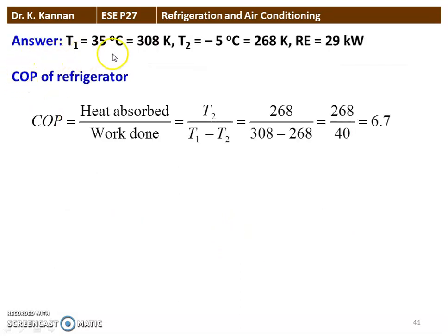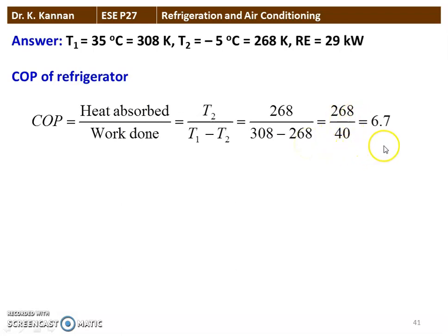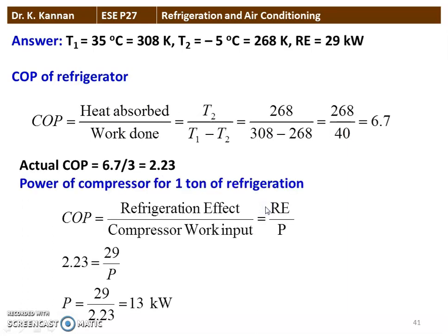The temperatures are T1 equal to 35 degree Celsius, which is 308 Kelvin; T2 equal to minus 5 degree Celsius, which is 268 Kelvin. The refrigeration effect equals the heat leakage, which is 29 kilowatts. The COP of the refrigerator based on temperature: COP equals minimum temperature divided by the temperature difference, so 268 divided by 308 minus 268, which is 268 by 40, equal to 6.7. The actual COP is one third of the theoretical COP, so 6.7 divided by 3 equals 2.23. Power of the compressor: COP equals refrigeration effect divided by compressor work input, so 2.23 equals 29 divided by power. Power equals 29 divided by 2.23, equal to 13 kilowatt.